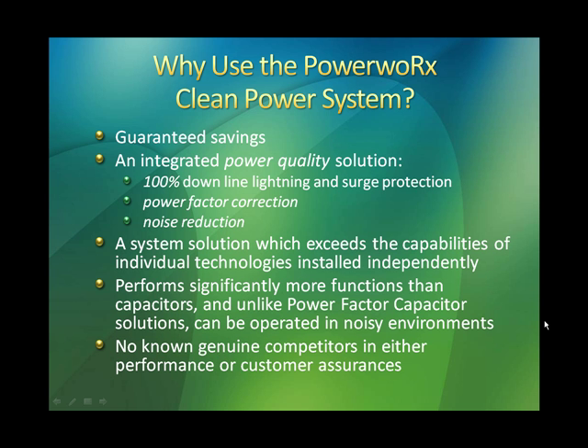So the synergy between these 3 technologies inside this box is greater than the sum of the 3 parts that have gone into it. Our intellectual property is not capacitors and MOVs and filters. The intellectual property is the way these are integrated together inside of the unit. The clean power system performs significantly more functions than capacitors, and unlike power factor correction capacitor solutions, can be operated in noisy environments. We've talked about the risk of capacitors when there are harmonics in the system going into a resonant condition. You don't have to worry about that with the PowerwoRx when it's properly installed. And there are really no known genuine competitors in either performance or customer assurances that are provided by Continental Power.